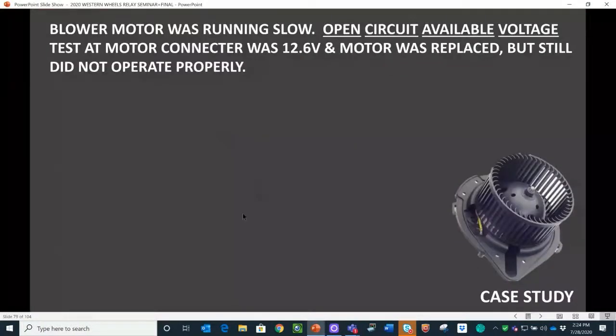A blower motor case scenario: it was running slow. They checked the open circuit voltage available at the motor, and it was 12.6. Yet the motor was still running slow. So they changed the motor, but it didn't fix the problem. Now, those of you that are sharp, and if we were in the classroom, I would ask, what's wrong with that diagnostic procedure? And you notice the words underlined are open circuit available voltage.